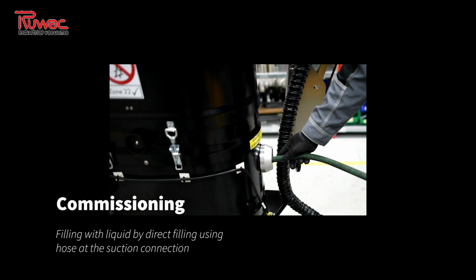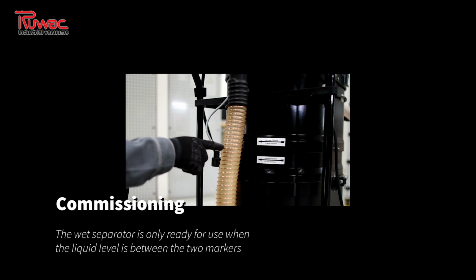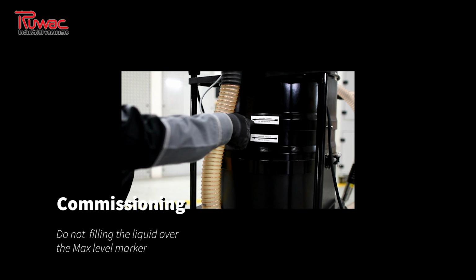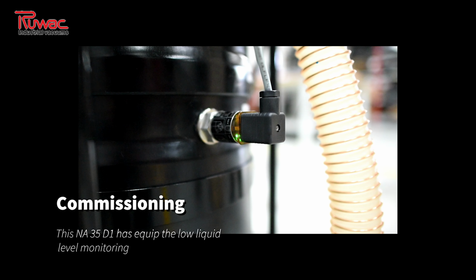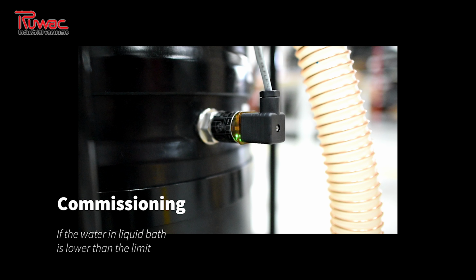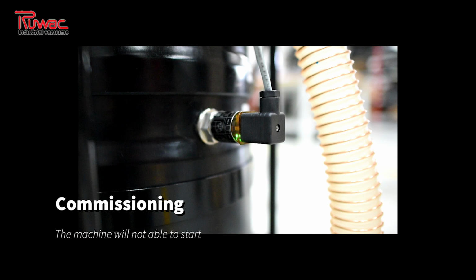Filling with liquid. By direct filling using a hose at the suction connection. The wet separator is only ready for use when the liquid is between the two markers. Do not fill the liquid over the max level marker. And this NA35D1 is equipped with low liquid level monitoring. If the water in the liquid bath is lower than the limit, then the machine will not be able to start as well.